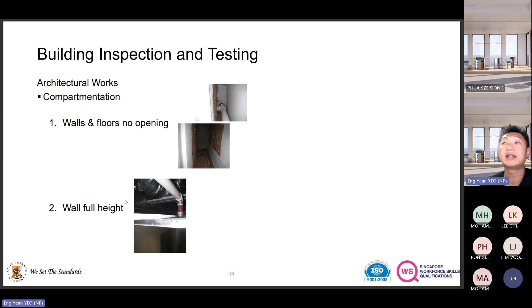That is the compartmentation we want to see. It's not just floor to ceiling - if you only go up to the false ceiling but not above it to the biggest area, the fire will just spread over to the other unit. So it's very important that if compartmentation is to be done, make sure it's full height.